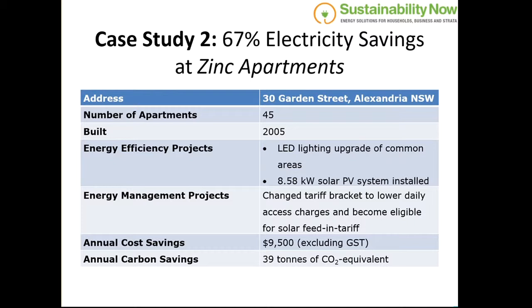That's right, only for common areas in this case. And that's the case for most apartment buildings, especially medium to high rise - there's just not enough roof area to cover the individual tenancies as well. But in this case, there probably is actually - they probably could do some tenancy stuff as well. But the issue becomes the Australian standards, and Ausgrid take a particularly rigorous view on this: if you have more than 30 kVA of solar connected to the same network connection point, then you have to have...